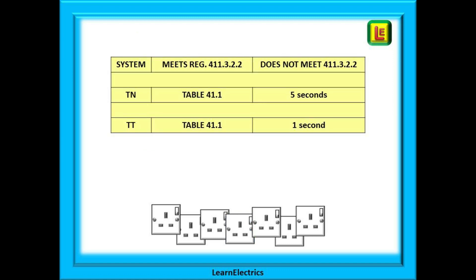Here we have put the last few slides into one summary table. If regulation 411.3.2.2 is met then we must use table 41.1. If it is not met, then we must use five seconds for TN systems and one second for TT systems.